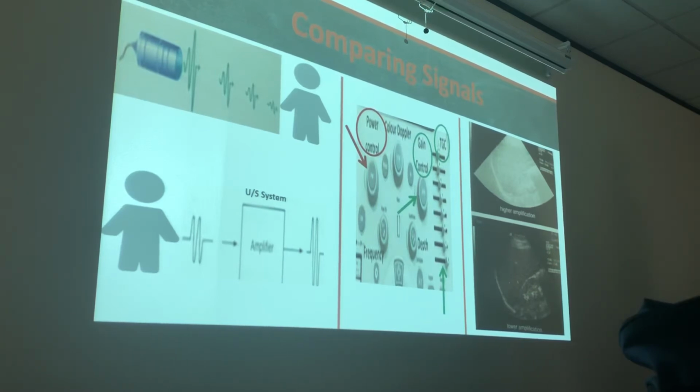We don't have that. What, acoustic power? We do. It's a knob. You can clearly see it on Toby, the machine, the first machine, number 1. It's right on the console. It's a big button on the front facing part, not the flat part. On the IU22, yes, it's on the touch screen. When you hit the next button, it's one of those knobs at the bottom. It has output power right there.